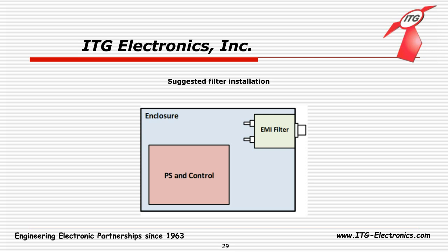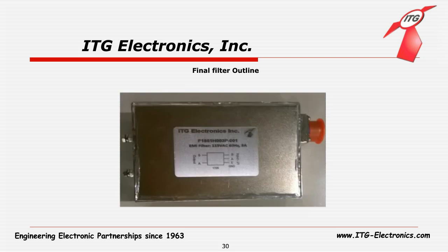Now, if you remember earlier, I mentioned my understanding of COTS filters. In most military applications, the COTS filter mechanical outline does not fit in the available volume. For example, in this case, we were asked to change the filter input termination to a mil connector mounted on a doghouse, which you can see here, and change the mounting brackets. If you remember, the earlier box had brackets on both sides, to inserts. So this is what the final filter package looks like. It is no longer a commercial off-the-shelf filter. It's a custom filter.